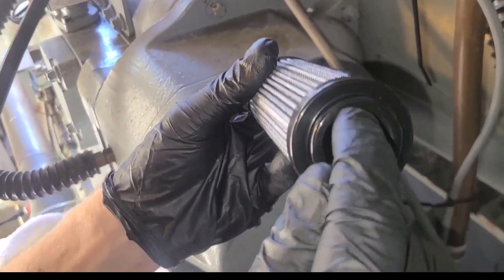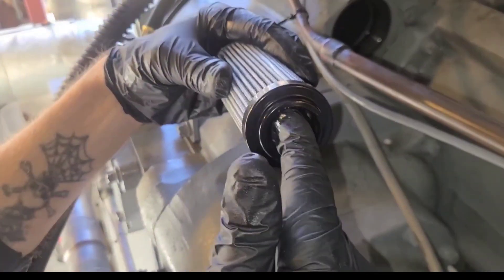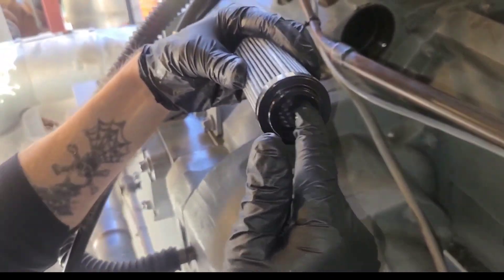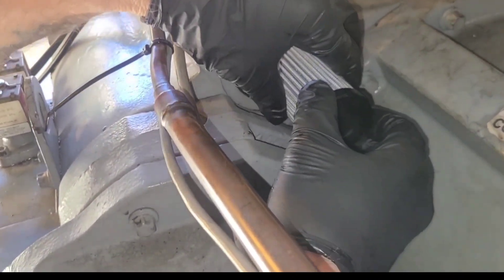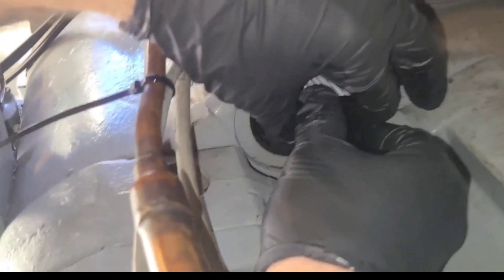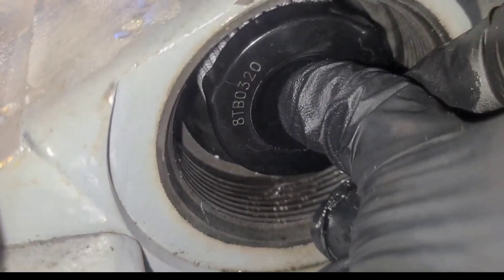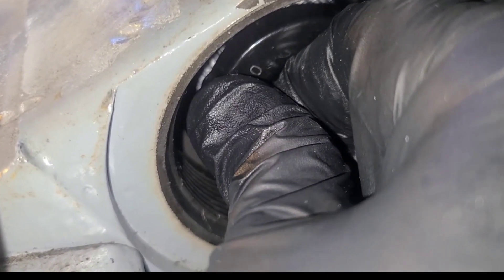Here's a brand new filter. Very important to oil this o-ring. Very important to lube the inner diameter o-ring. Install it in reverse of the way we removed it. It's a snug fit. You will feel it go in and stop.